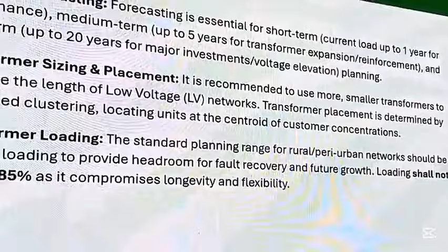Transformer sizing and placement. One thing that was not common initially in the LEC network, but is very common nowadays, is the use of very large transformers, which is logical. I can understand why they are using large transformers, because of population density in some areas and the demand in some communities. But the challenge is the tendency to continually extend the length of the low voltage network without taking into consideration voltage drop along the line. So we are recommending using smaller transformers to minimize the length of the LV lines where possible.